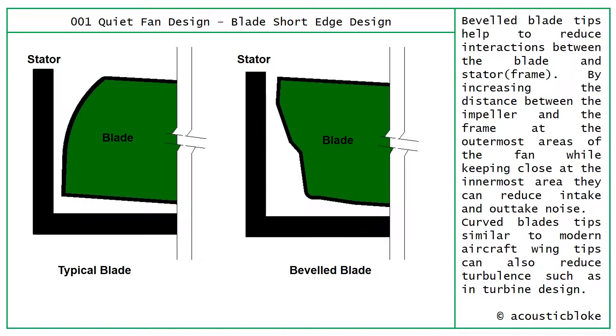Looking at the fan on its side, where the blade comes into close proximity with the stator: a typical blade system leaves a slight gap at the top and sits as close as possible at the bottom. Beveled tip blades help to reduce interaction between the blade and the stator or frame. By increasing the distance between the impeller and the frame at the outermost area while keeping it close at the innermost area, they can reduce intake and outtake noise. Curved blade tips, similar to modern aircraft wingtips, can also reduce turbulence, as seen in wind turbine design.